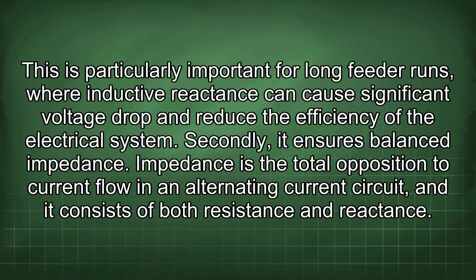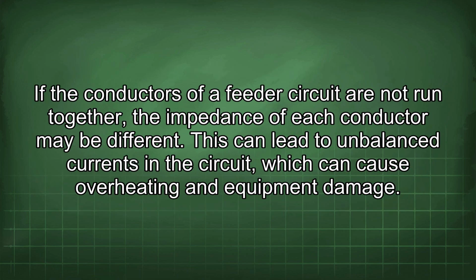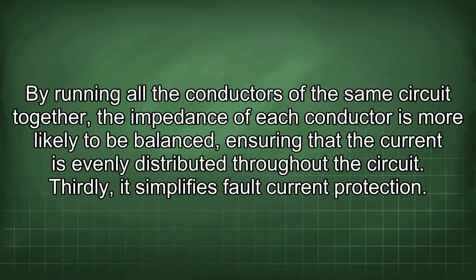of the electrical system. Secondly, it ensures balanced impedance. Impedance is the total opposition to current flow in an alternating current circuit, and it consists of both resistance and reactance. If the conductors of a feeder circuit are not run together, the impedance of each conductor may be different. This can lead to unbalanced currents in the circuit, which can cause overheating and equipment damage. By running all the conductors of the same circuit together, the impedance of each conductor is more likely to be balanced, ensuring that the current is evenly distributed throughout the circuit.